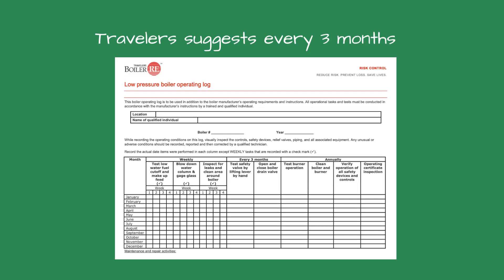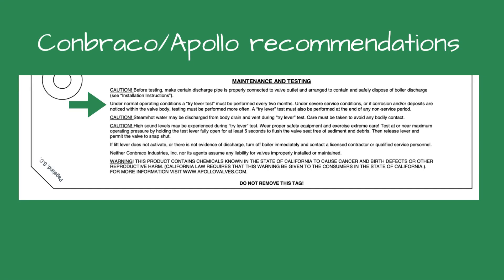How often should you test the pop safety valve? I recommend contacting your insurance company because they are ultimately responsible if it fails. The safety valve manufacturers can also give you guidance — one manufacturer suggests once a year, another suggests twice a year. Conbraco and Apollo recommend every two months and at the end of a non-service period — whatever that means.